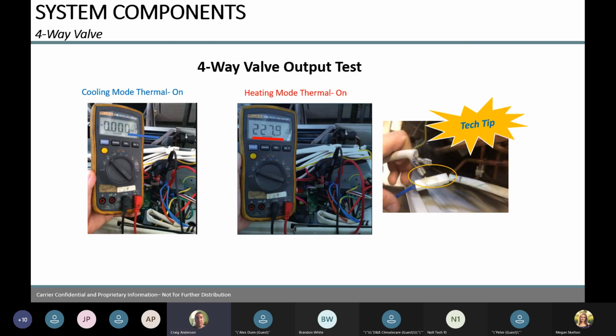The other thing you're going to run into, and I think most of the sales now, are units that have heat pumps with reversing valves put into them. On our outdoor unit, the reversing valve is energized in heating mode, not cooling mode, whereas on a lot of units the reversing valves are energized in cooling. So if you're checking the heating system and need to check the reversing valve, you're looking for voltage when it's going into heating and no voltage when we switch it back over to cooling.